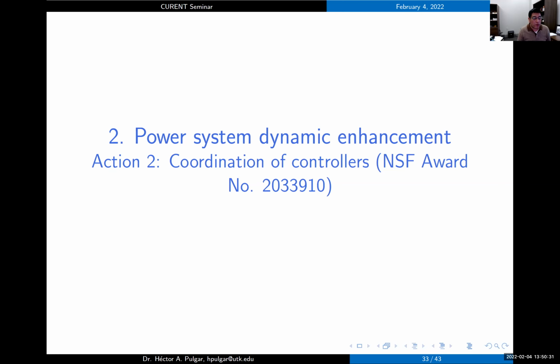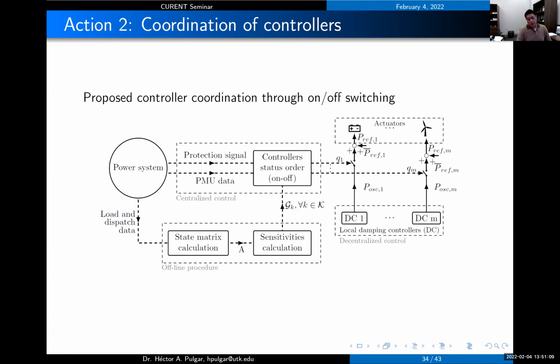Therefore, if you have a controller designed for that mode, the mode is not there. So the controller will have some action, but it's likely that that action will make things worse, because it was designed to damp an oscillation mode that is not there. So we realized that we actually need some sort of coordination when you have these controllers, because the excitation of a mode is something that we cannot anticipate. It depends on the fault disturbance in the system, and this can be anywhere in the system.